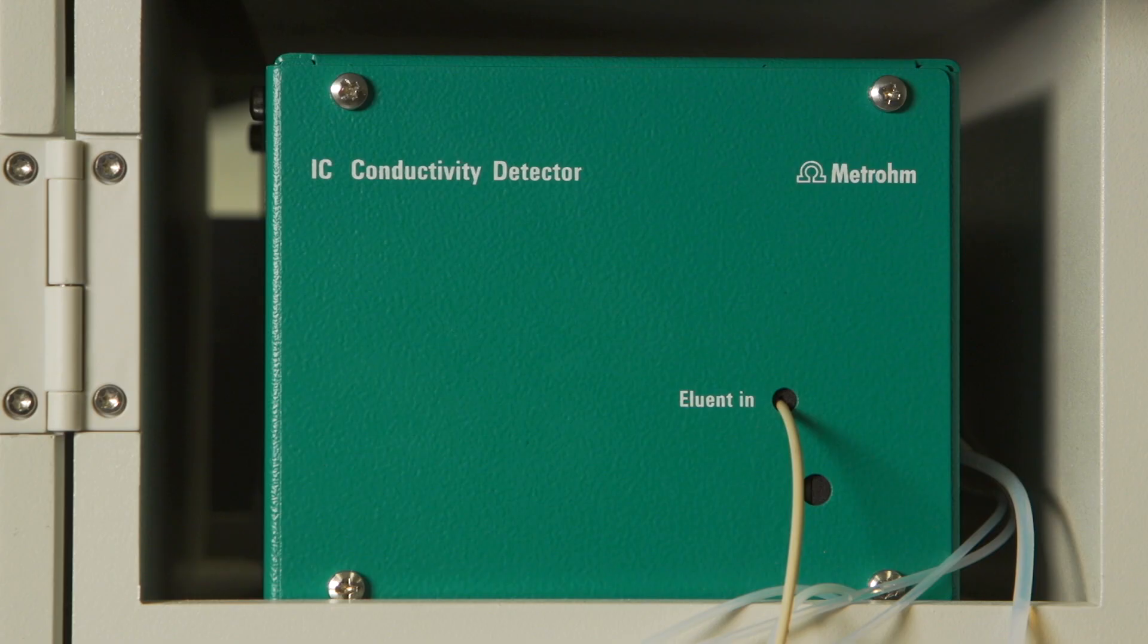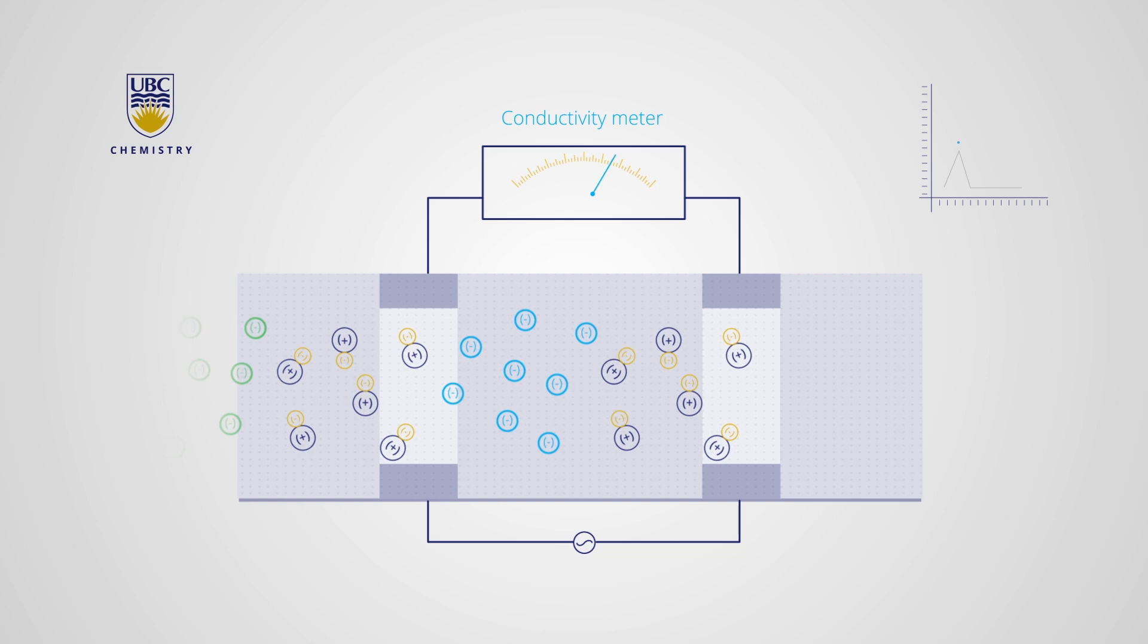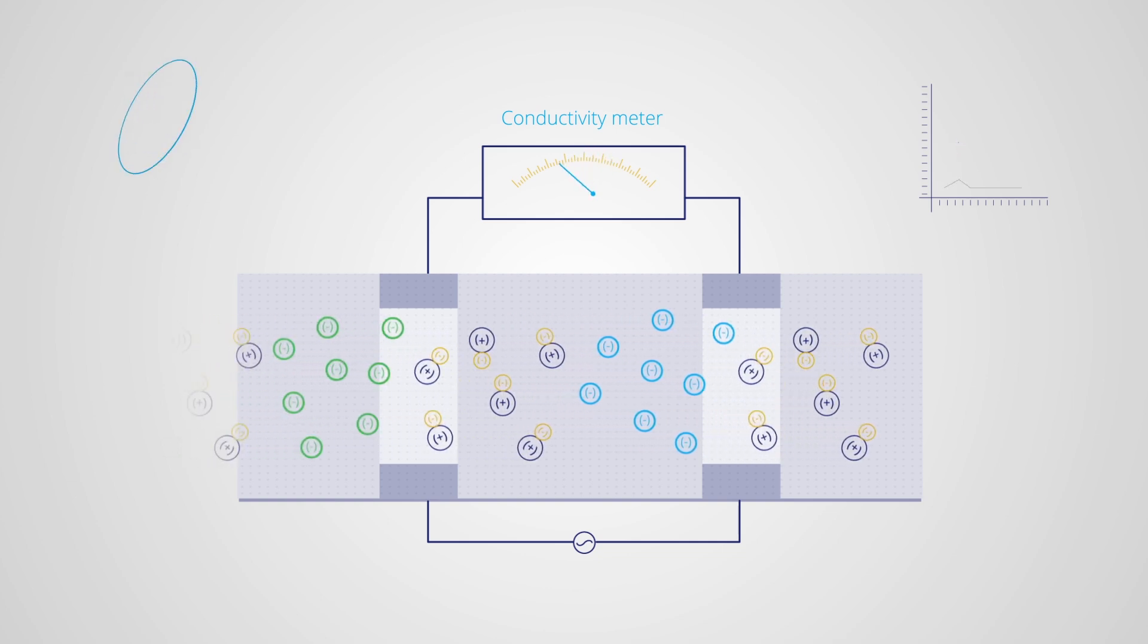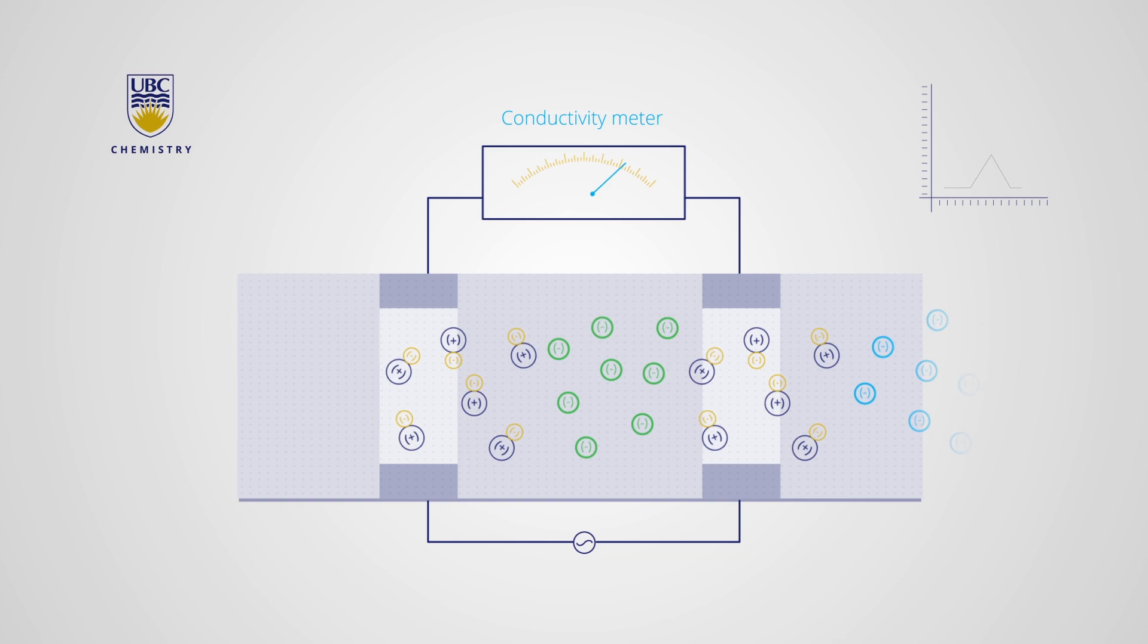The sample coming out of the suppressor reaches the conductivity detector. The ions enter a flow cell containing two electrodes, which have a potential applied across them. As the ions pass through, a current flows. The current is proportional to the conductivity, which is related to the ion concentration.